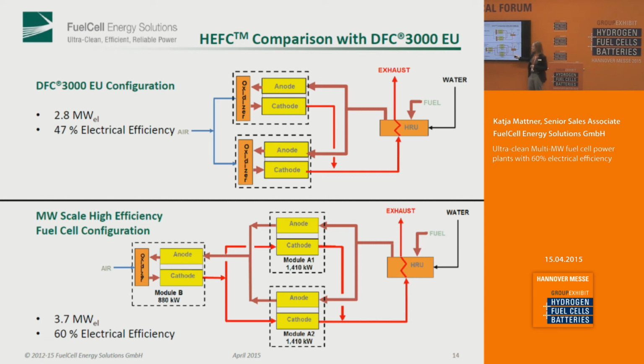The heat is recovered here, used to preheat the gas. What's new now is that fuel comes again into the heat exchanger, getting preheated, going to the anode, but now the stream is led to another module, the third one you've seen before. Here there's the process with the oxidizer, and then the stream goes backwards to the cathode, through the cathodes of the first modules as well, and back to the heat recovery unit. So here we reach 3.7 megawatts with an electrical efficiency of 60%.